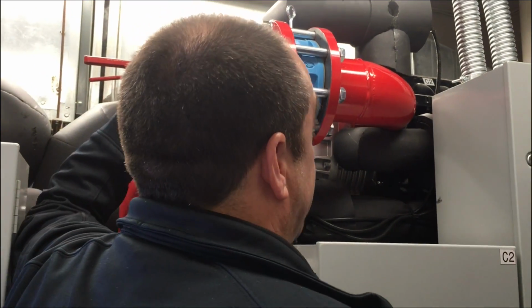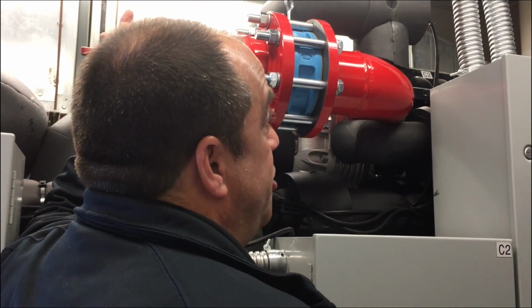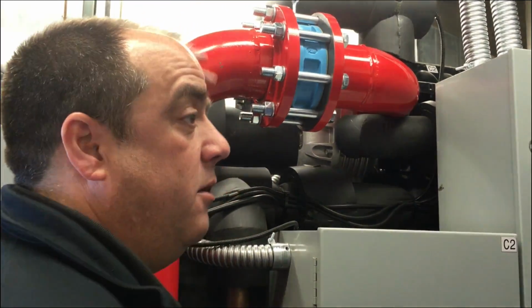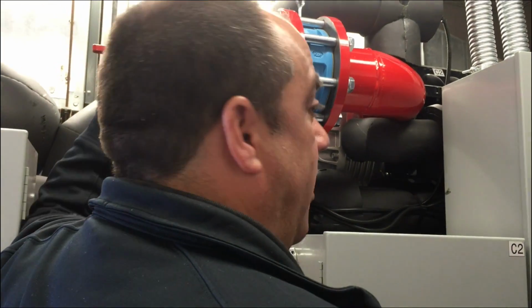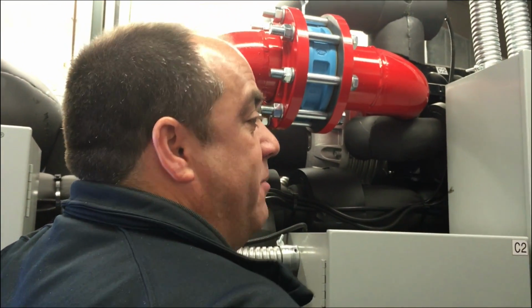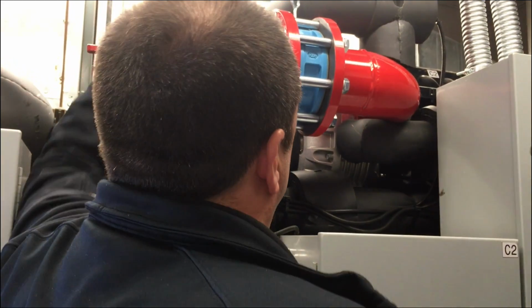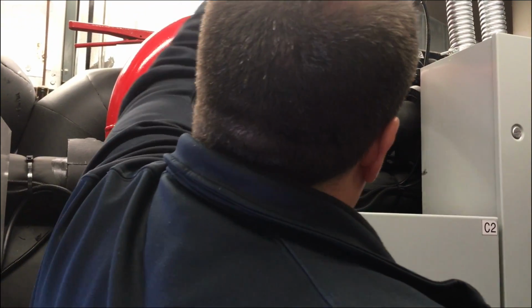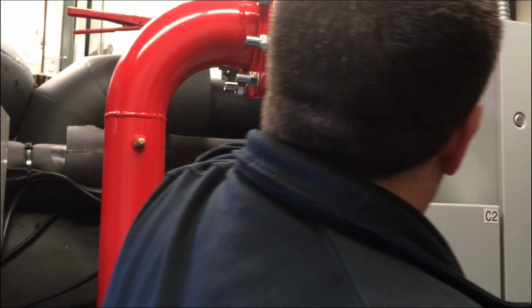And because of that, you get really high energy numbers even if you do a lot of cycling, compared to a chiller that was dimming the lights and bringing in double contactors and drawing 300 amps every time it started. So this guy spins in a circle, gas comes in the suction, up the discharge, right back out into the suction, so it gets up to speed.